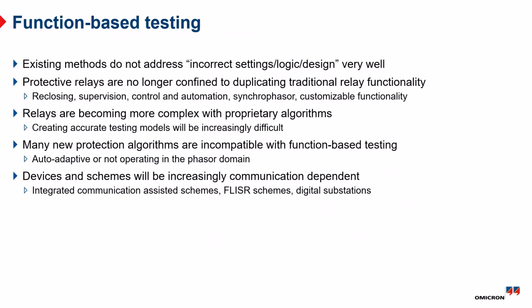So as I've alluded to, the existing methods really don't address the incorrect settings, logic, and design that misoperation reports highlight, right? Those are responsible for a third of the misoperations. And if you test in a really traditional way, unless you're extraordinarily careful, use different sources other than the relay settings to build your test, and test all the decision points and the logic independently, which is a lot of extra work, you're not going to do a very good job of detecting incorrect settings, logic, and design. You can tell from the misoperation report that the industry doesn't do a very good job of that, at least at this particular point in time.